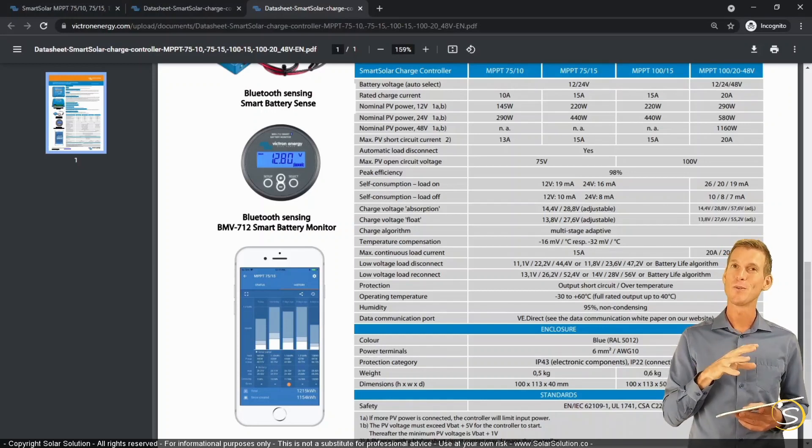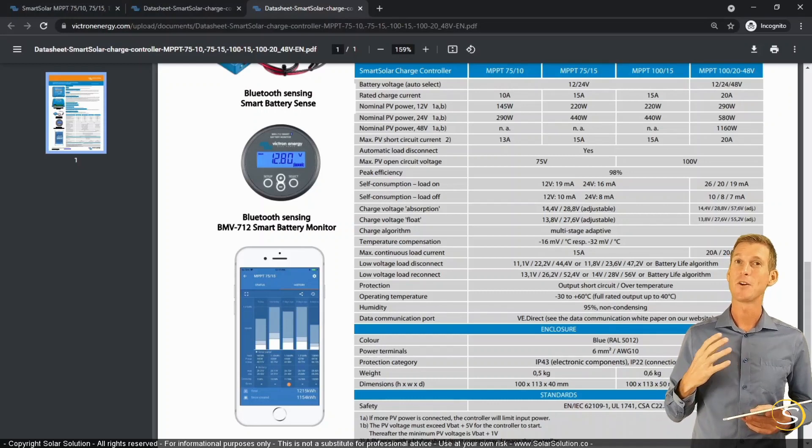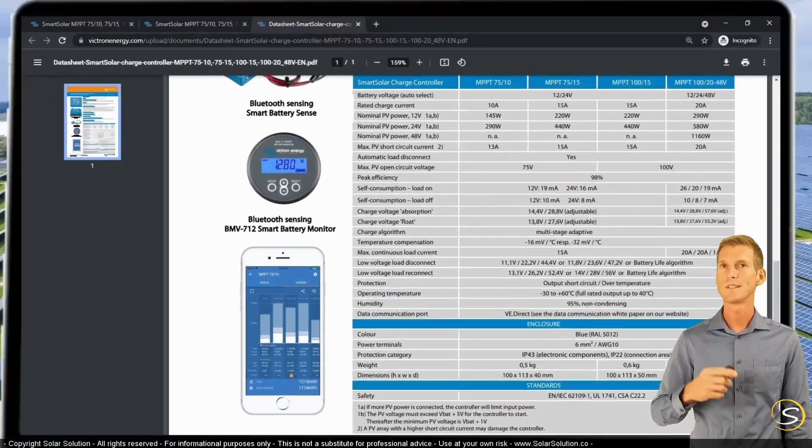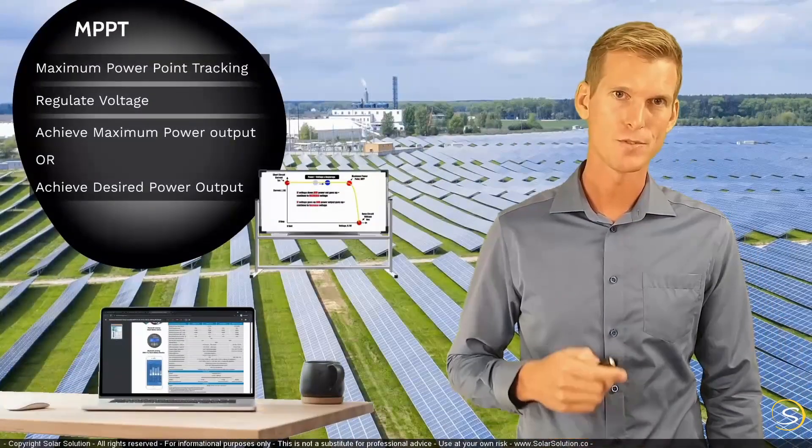realize that the open circuit voltage of a panel is also heavily influenced by the cell temperature. Because if a module is colder, it will actually produce a higher open circuit voltage. The voltage of a solar panel is higher when the cell temperature is lower.